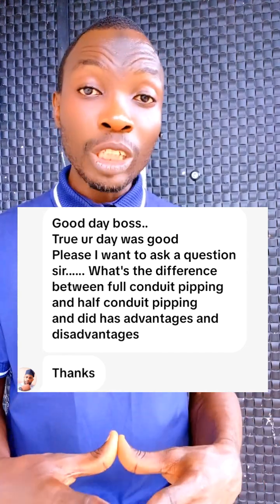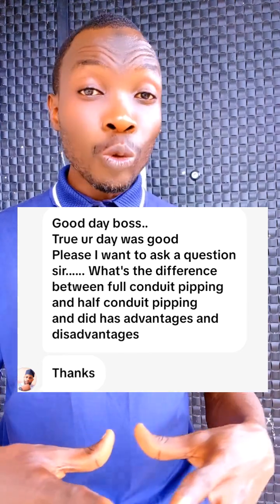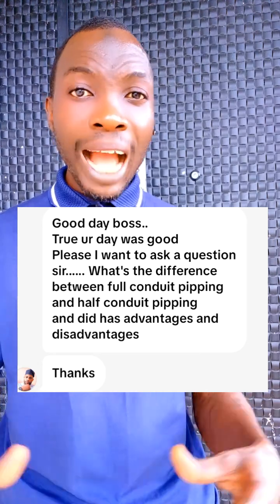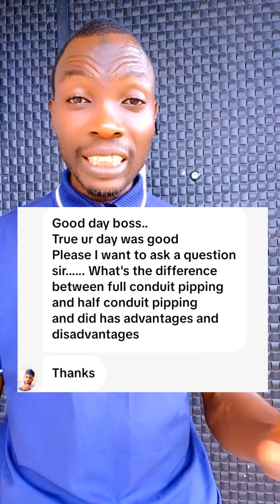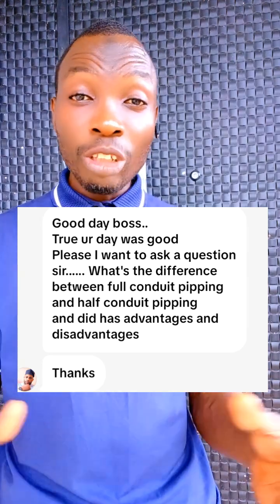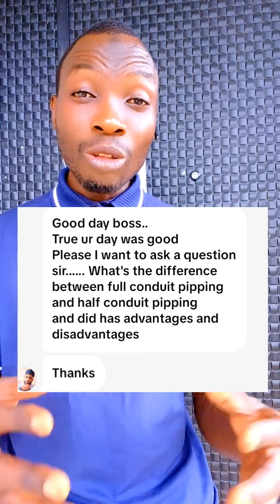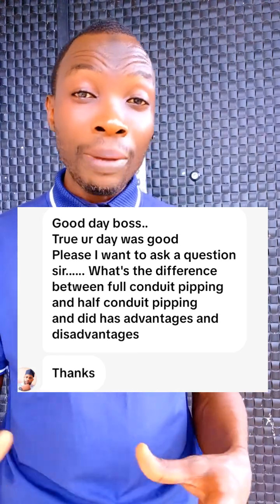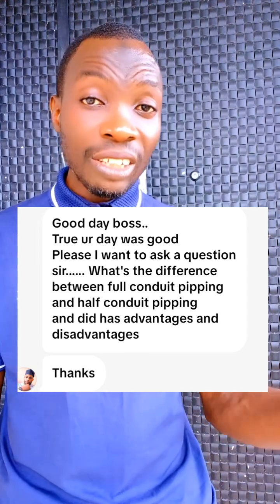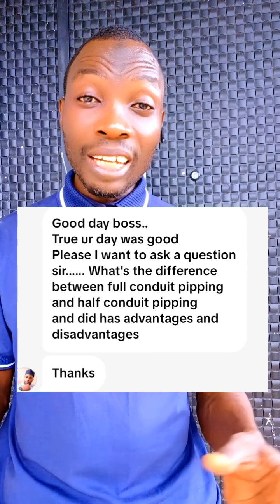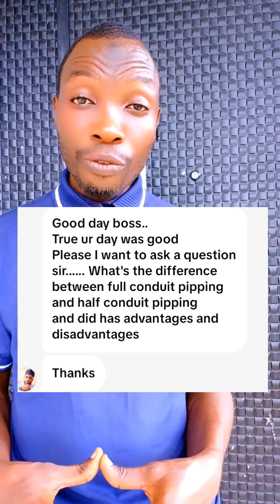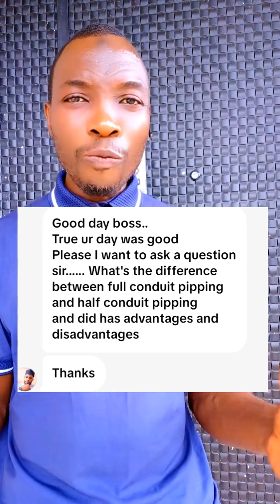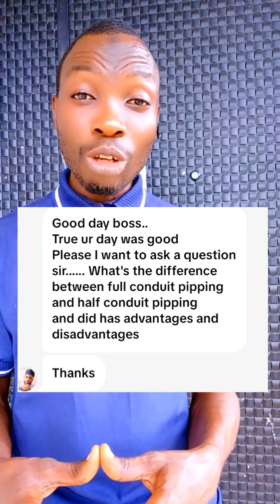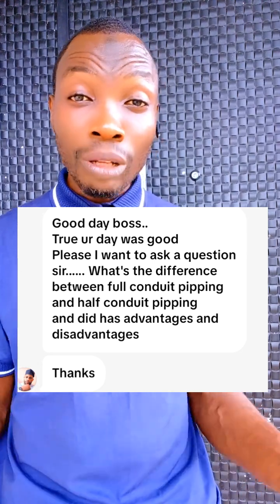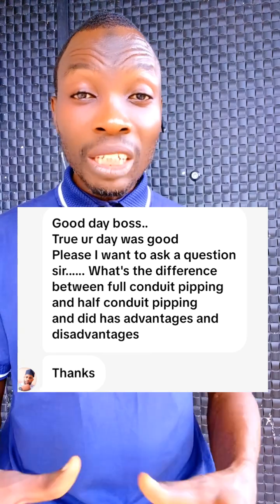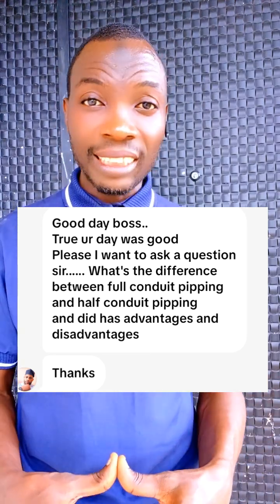Most people choose half conduit simply because they want to reduce the cost of installation. When you look at it, the difference between half and full conduit is just the cost of the pipe, which is nothing compared to the future problems that may arise as a result of leaving your cable dangling or running open in the roof. It causes a lot of problems. It makes fault tracing difficult, it makes the replacement of cables difficult, and it exposes cables to rodents.